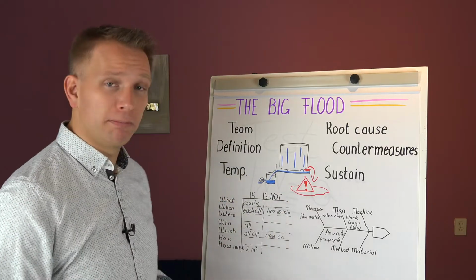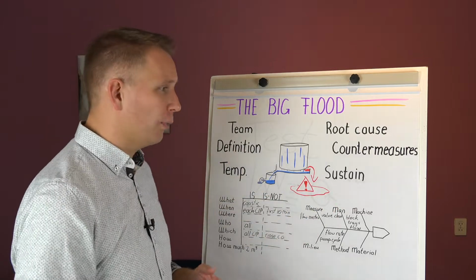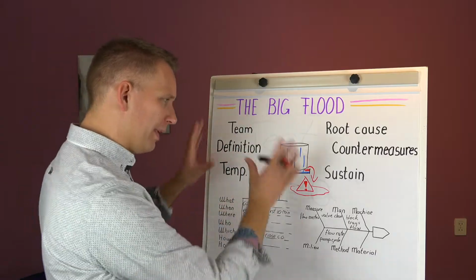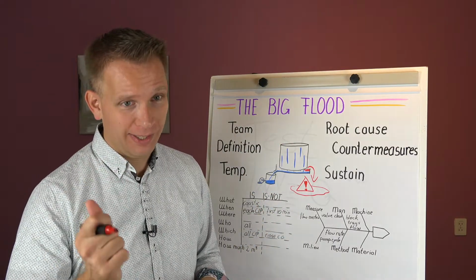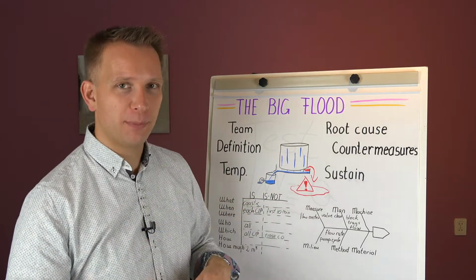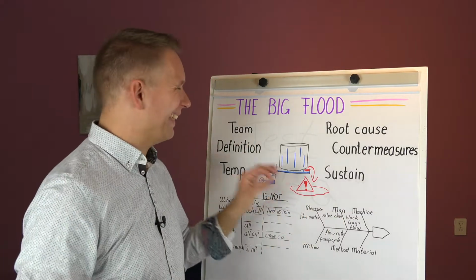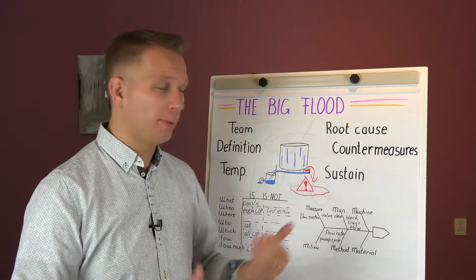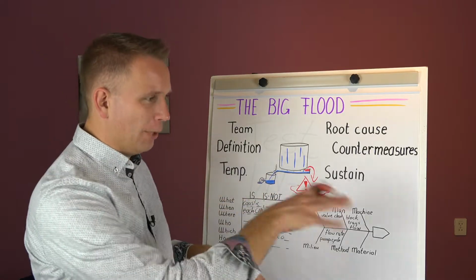Now, what did we see? It was about 2 cubic meters of liquid going over the floor, and we could measure this by the in and out flows and so on. We also did, with good safety equipment, go into that area, install some cameras, made some videos from further away, but also installed cameras that could really get footage of what was happening during the cleaning and when the problem occurs. And we saw some lower areas of this tray would overflow.